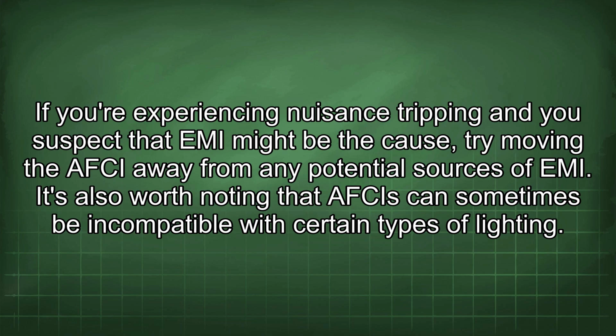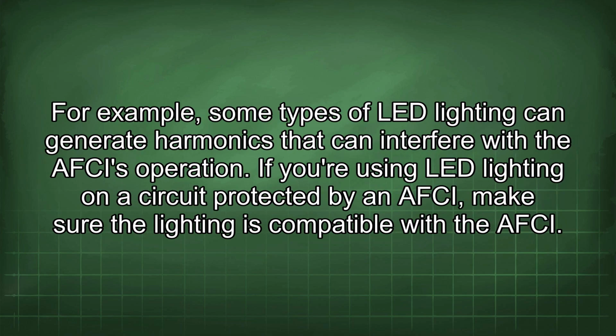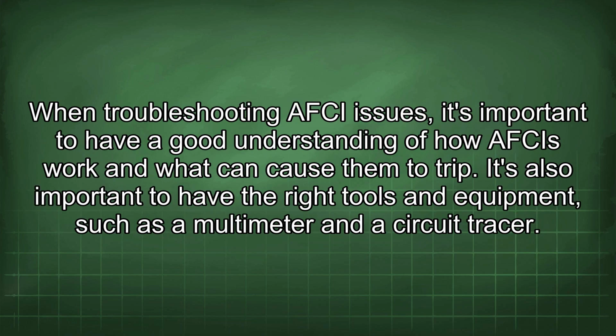It's also worth noting that AFCIs can sometimes be incompatible with certain types of lighting. For example, some types of LED lighting can generate harmonics that can interfere with the AFCI's operation. If you're using LED lighting on a circuit protected by an AFCI, make sure the lighting is compatible with the AFCI.